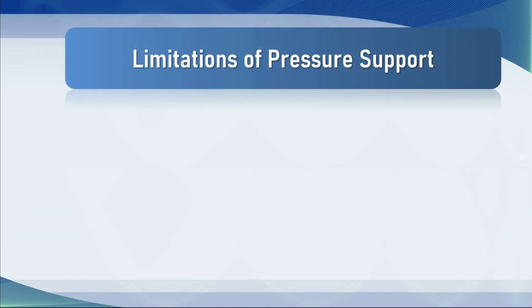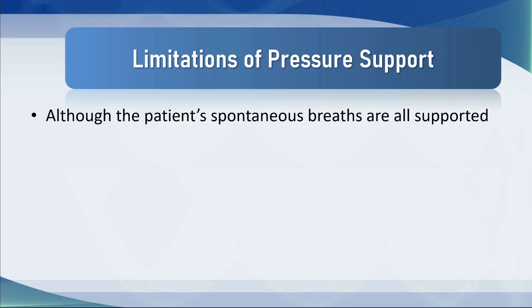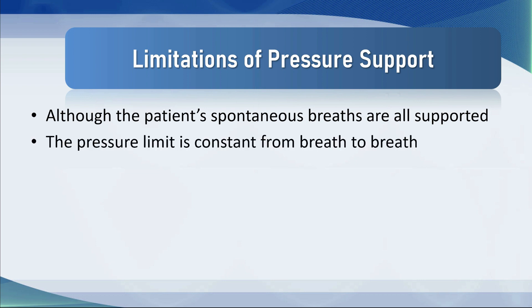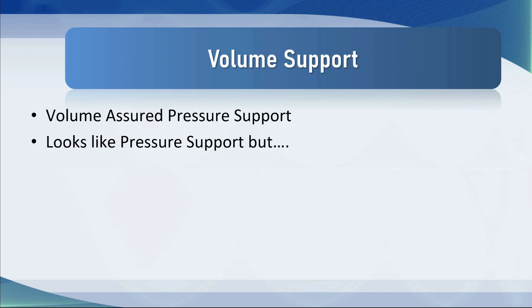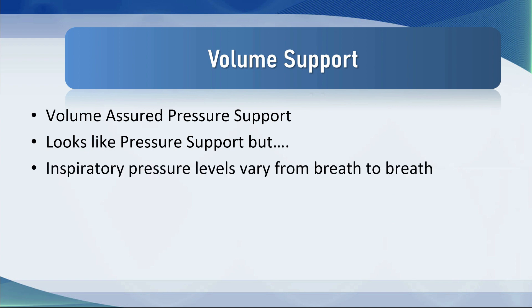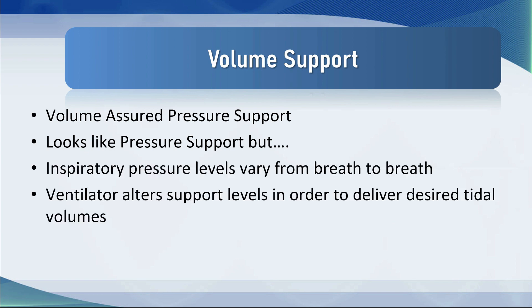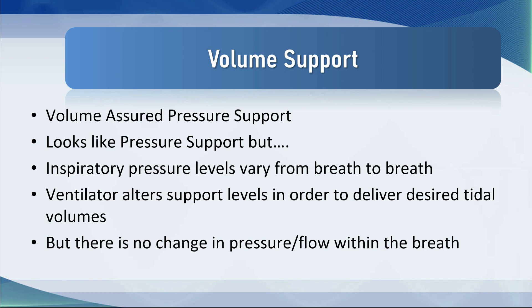Pressure support is a marvelous mode of ventilation but it has several limitations. Although the patient's spontaneous breaths are all supported, the pressure limit is constant from breath to breath, although tidal volumes can be quite variable. If a patient deteriorates the tidal volumes will drop with deterioration of lung compliance. Conversely, if the patient's lungs improve, the tidal volumes may be absolutely enormous. The idea of volume support is volume assured pressure support — it looks like pressure support, but the inspiratory pressure levels vary from breath to breath, and the ventilator alters support levels to deliver the desired tidal volumes. Compared with automatic tube compensation, there is no change in the pressure-flow relationships within the breath; things change from breath to breath but not within the breath.